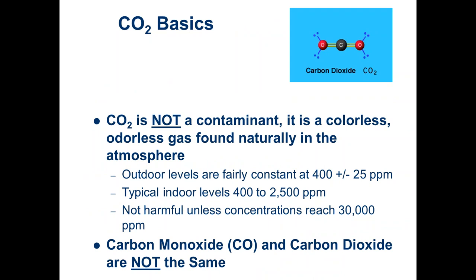CO2 is not a contaminant in a normal building. You can get up to 30,000 parts per million before any health concerns. I've never seen a building go above 2,000 PPM, and breathing directly on a sensor I could only get into the 5,000s. You cannot get CO2 levels in a building so high as to be a health risk unless it's a weird manufacturing facility. So it's not a contaminant and not dangerous in the built environment.